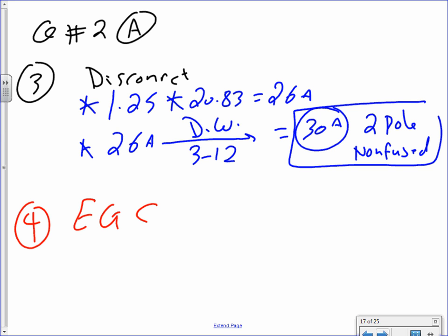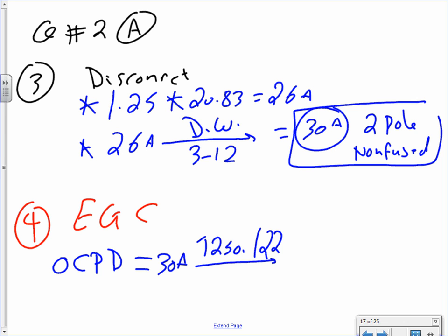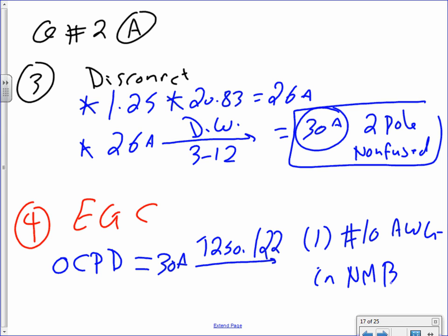The last thing, the equipment grounding conductor, is very easy, guys. You take the overcurrent protection device that you have just come up with, which is 30 amps. Take this one to table 250.122 and that will get you a healthy one conductor number 10 AWG in an NM cable. Remember, we're using a cable, so it will be part of the NM cable. You don't have to pull a separate one. Does that make sense, Matt? You're not pulling a new one. There's a cable. Two of them are going to be 2 hots and an equipment grounding conductor number 10.